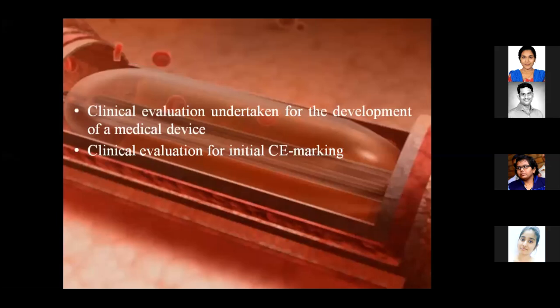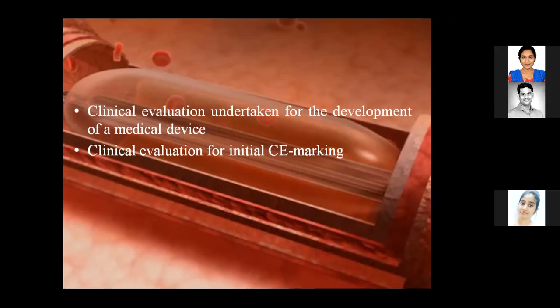In development, pre-marketing research and development are guided by clinical evaluation and risk management, which define needs regarding clinical safety and clinical performance of the device. In case of possible equivalence to an existing device, evaluate if there are clinical data available and determine equivalence, with additional information, to the existing device. CE marking: clinical evaluation is required for the conformity assessment process leading to the CE marking and placing the device on the market. Document that there is sufficient clinical evidence to demonstrate conformity with the essential requirements covering clinical performance and clinical safety.